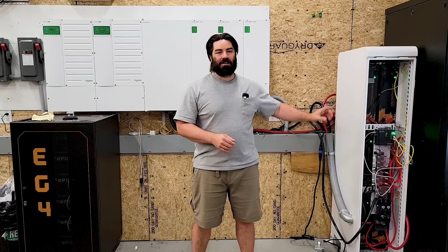The manual says this battery bank can handle 500 amps continuously. When I tested an individual battery on the workbench, it passed all the specifications with flying colors. Now we have 6 batteries wired up in parallel in the cabinet, and I'd like to do one more test in the cabinet: a continuous current test.